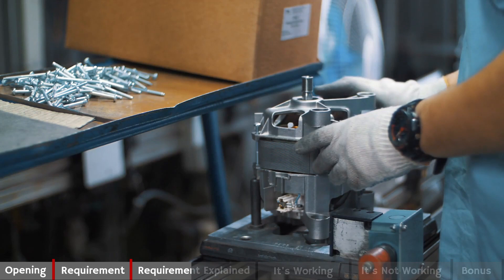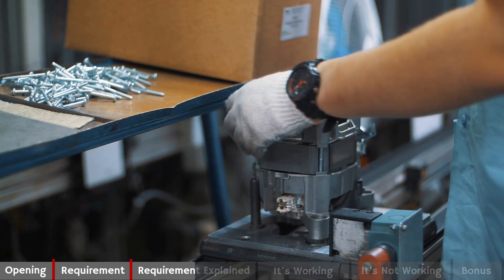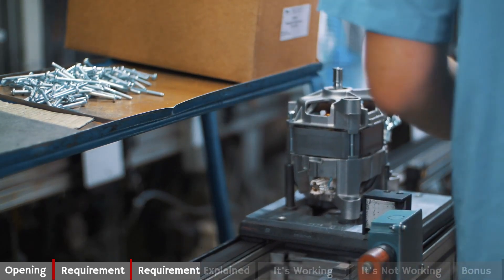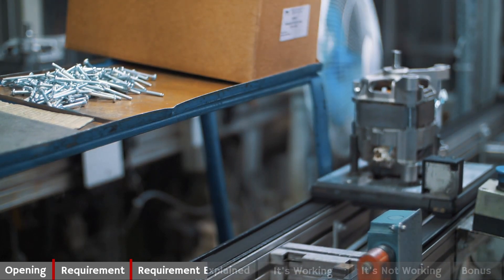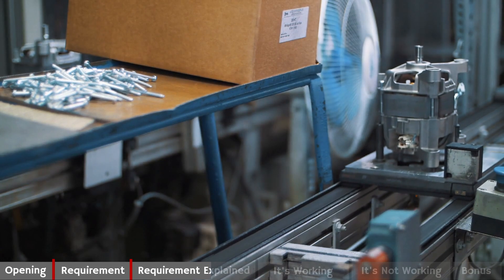Servicing personnel have to be trained to the servicing procedures and they also have to understand the customer's requirements. Service reports have to be fed into the CAPA process where they are tracked and trended. Service reports also have to be reviewed to determine if they are a complaint and also if that complaint is reportable.